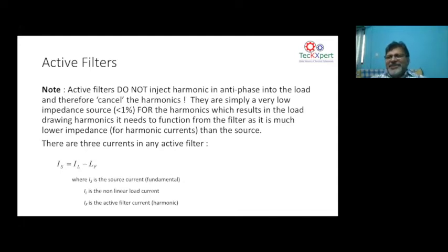That's a most electrical engineering way of explaining an active filter. Now you can see, in the active filter, IS is the source current, that is the current flowing in from the transformer, and IL is the load current, which is the load connected to the transformer, and IF is the filter current. Now you can see IS, the source current from the transformer, is reduced to the extent of IF. IS is IL minus IF. That is the equation. That means the source current is reduced. That is how an active filter will protect the transformer from absorbing harmonic currents from the network.